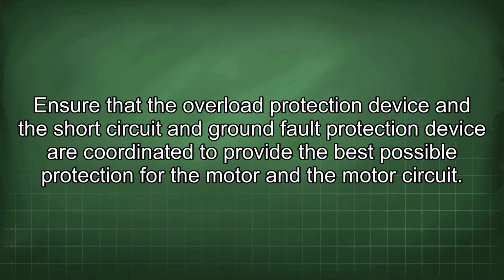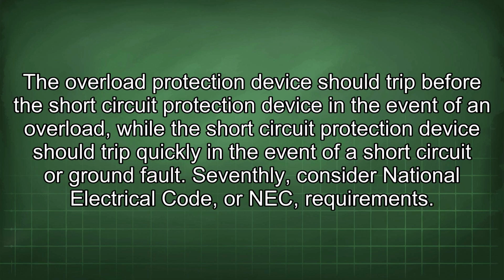Ensure that the overload protection device and the short circuit and ground fault protection device are coordinated to provide the best possible protection for the motor and the motor circuit. The overload protection device should trip before the short circuit protection device in the event of an overload, while the short circuit protection device should trip quickly in the event of a short circuit or ground fault.